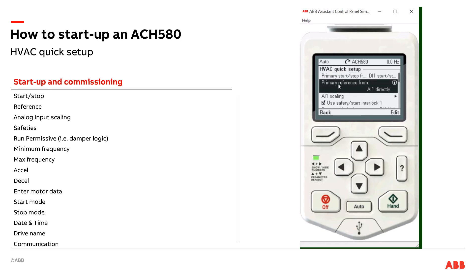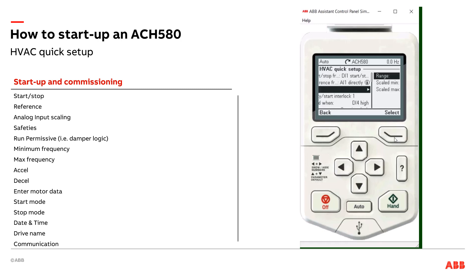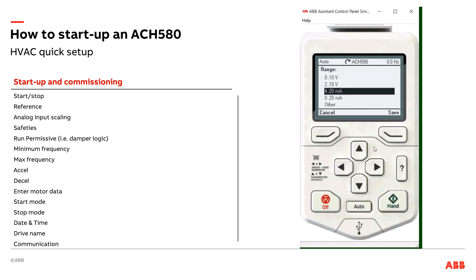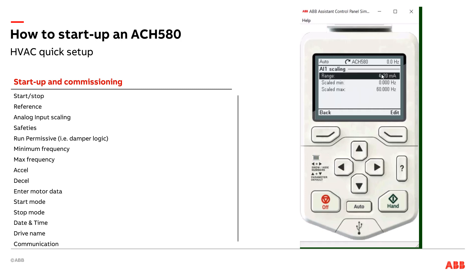Similarly for analog input one — where am I getting my speed reference from? Factory default is analog input one. I can set that to BACnet if I wanted to do my speed control over BACnet as an example. Taking a look at my analog input one scaling, I'm going to hit select. This is where I choose: is this a 0 to 10 volt signal or is this a 4 to 20 milliamp signal? I can change that to 0 to 10 or 4 to 20. Factory default happens to be 0 to 10. I'd previously changed this to 4 to 20 milliamps, so 4 to 20 milliamps equals 0 to 60 hertz. I can back out — my scaling is good to go.